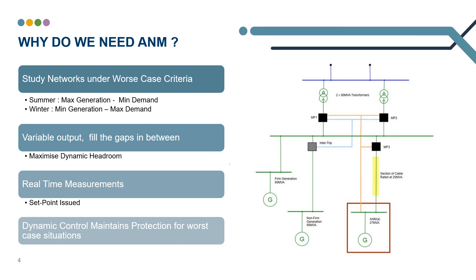In reality, though, these connections are not always going to be running at 90 MVA. Additional actively managed generation can be dynamically controlled to maximize the available capacity. If we monitor the real time current flow through the highlighted points, we can assign a set point value to fill the gaps between the existing connections. Without the use of ANM, we'd be unable to connect this capacity as we had no protection under the worst case scenarios.